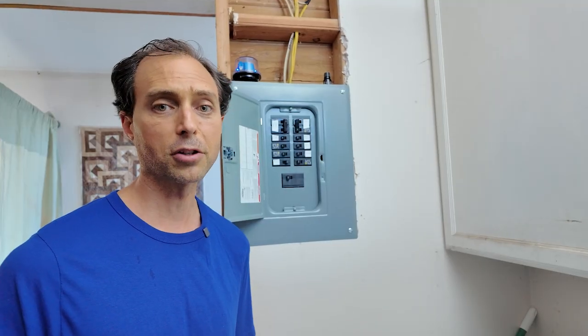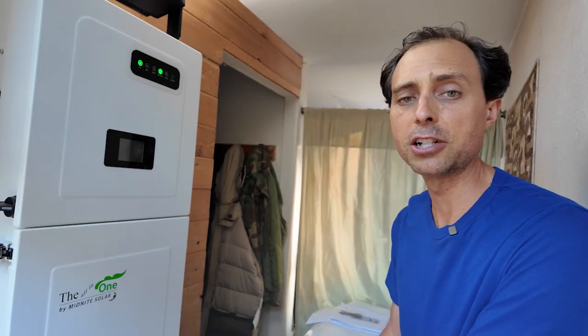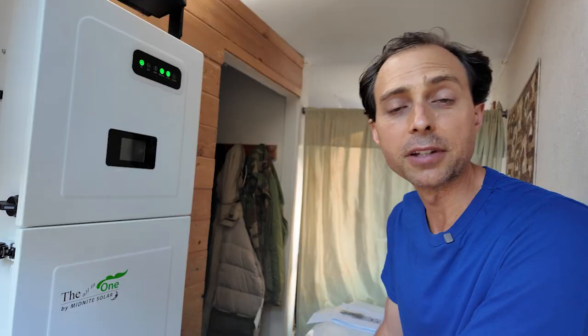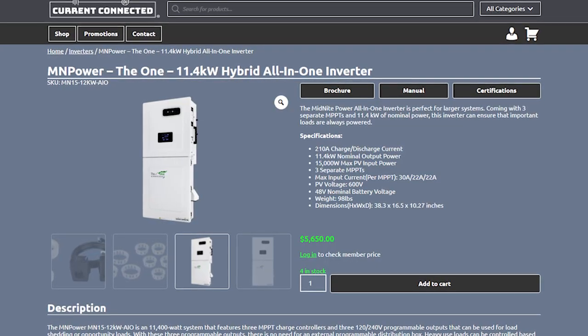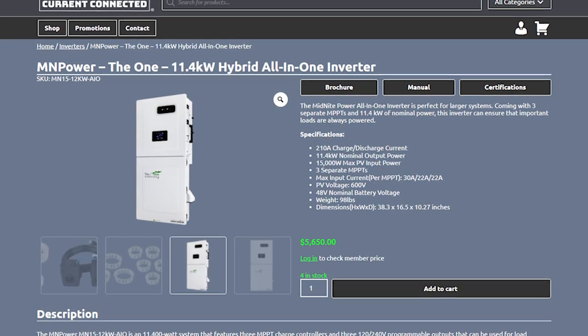Sol-Ark makes a solid inverter, but the expectations created by this 200-amp pass-through marketing are where things fall apart. That spec is technically true, but the application is misleading for anyone planning on going off the grid. Since I'm completely off the grid, I have to have a system that is totally functional and reliable — there is no grid here. That's why I chose the MidNite Power all-in-one inverter. Unlike most brands, MidNite didn't chase marketing numbers. Their system has a much more realistic 100-amp pass-through — not because it's weak, but because they wanted to be honest about how much load their 10-kilowatt inverter can realistically handle off the grid.